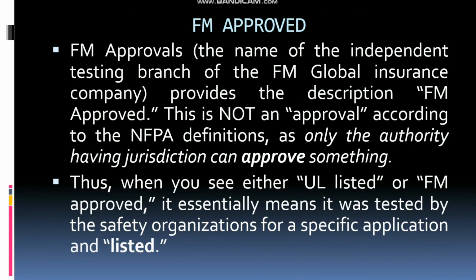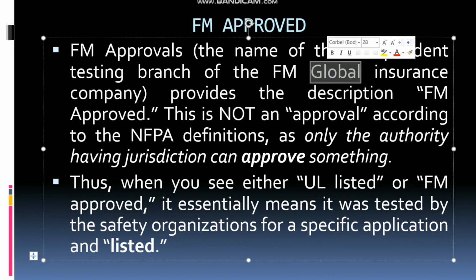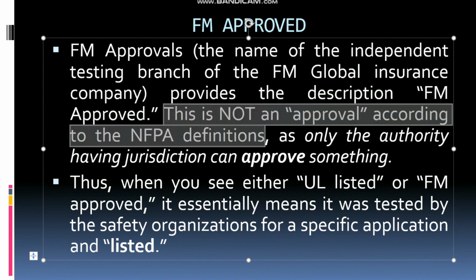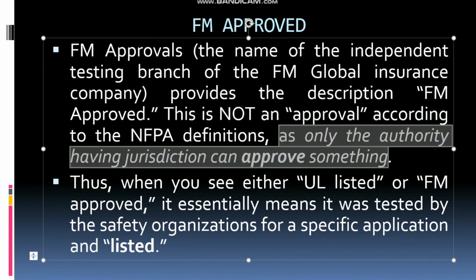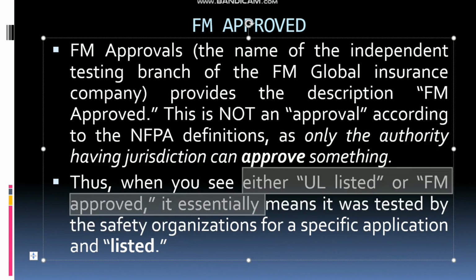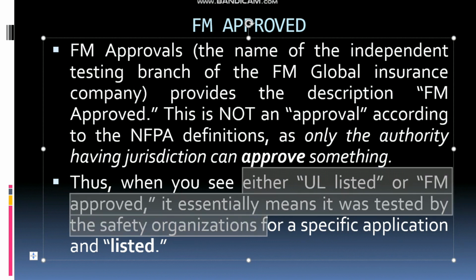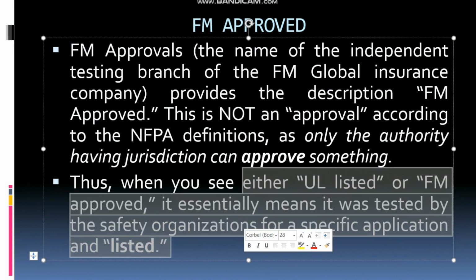So next one is the FM approved. So FM approval, as you know, is a branch of the FM Global Insurance Company. So it has again some set of rules. If you follow those, then your product will get FM approved. So again, this is not an approval according to the NFPA definition, because we know that the NFPA definition of approval means something different, as only the authority having jurisdiction can approve something. So these two approval words are similar, but the concept, as you know, is different. Thus, when you see either UL listed or FM approved, it essentially means it was tested by the safety organization for a specific application and it is listed. That's all.